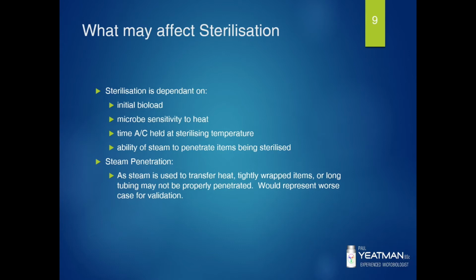And when you validate a cycle of 20 minutes at sterilisation temperature, running the sterilisation cycle for 10 minutes won't guarantee sterilisation. So you've got to make sure that if you validate for time equals X, that is the minimum time they actually do to validate the autoclave cycle for.